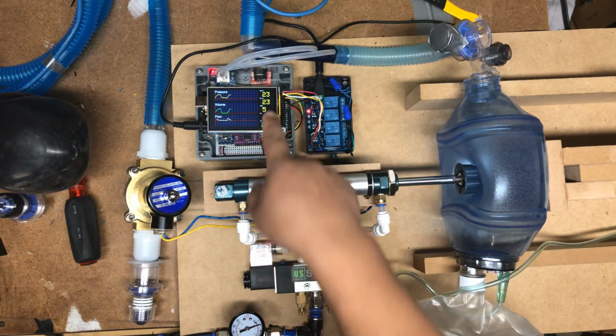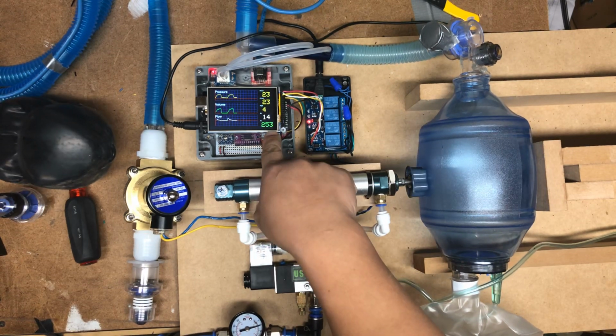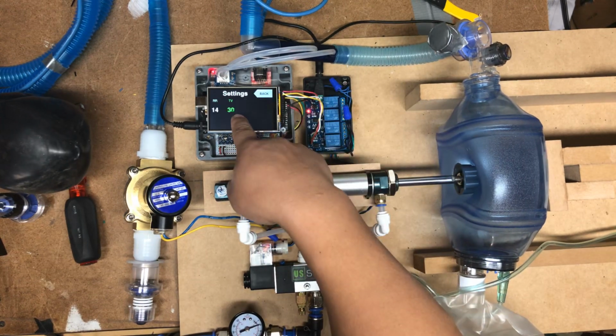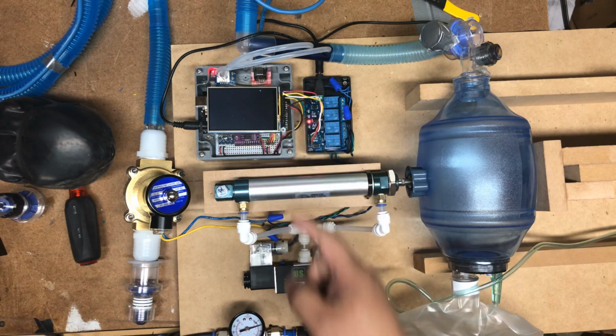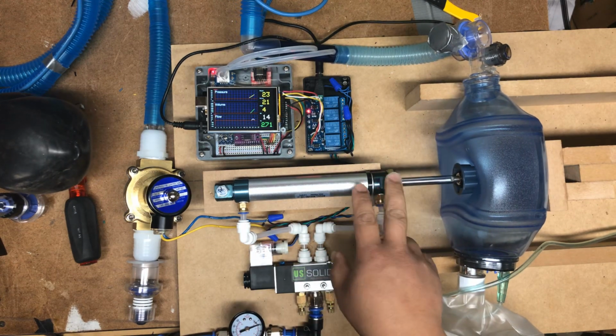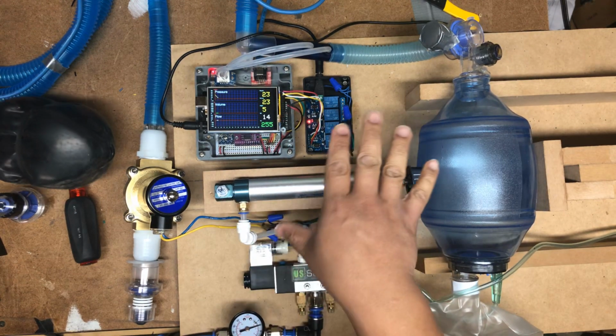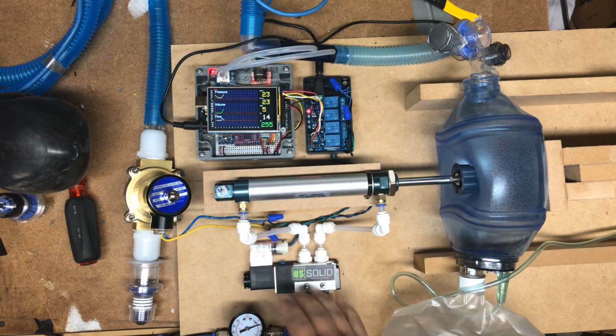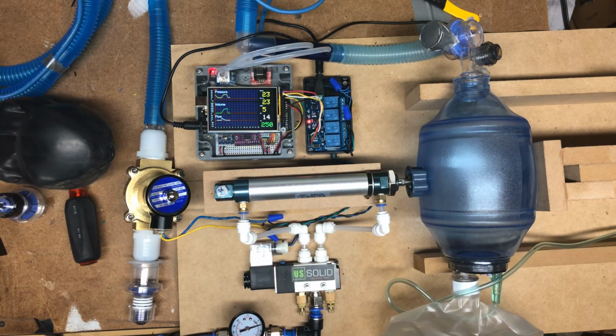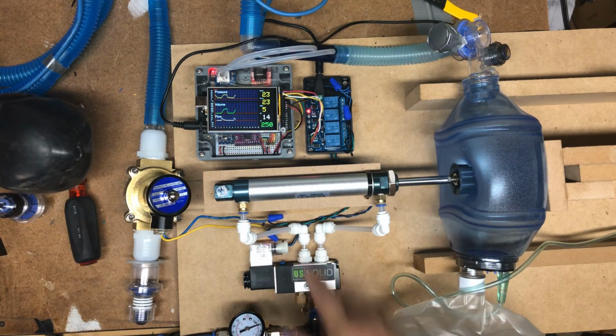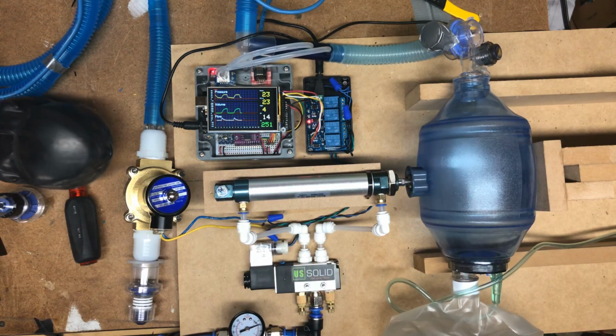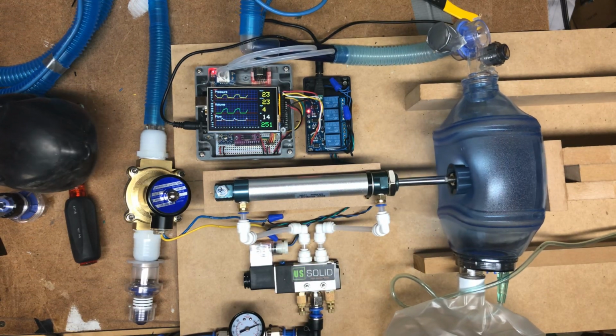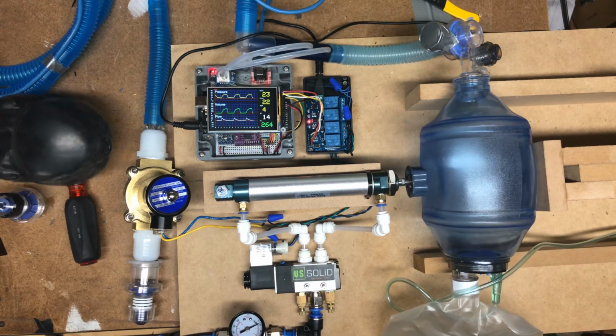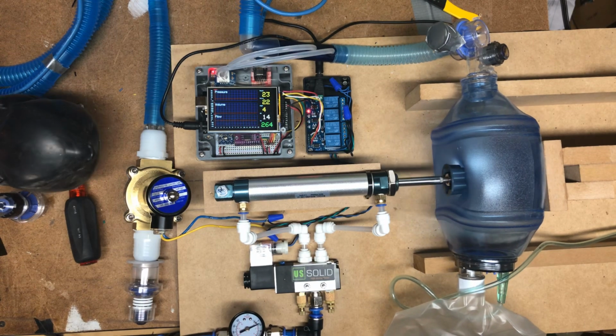At this pressure level, we're unable to achieve our set tidal volume, just not enough pressure, so once we get the alarms added, it will indicate a kind of yellow alarm saying that tidal volume was not achieved at this pressure. But you can see there's very good pressure control there.